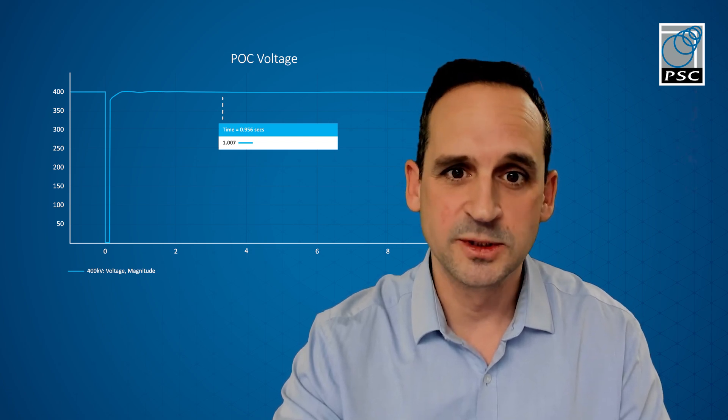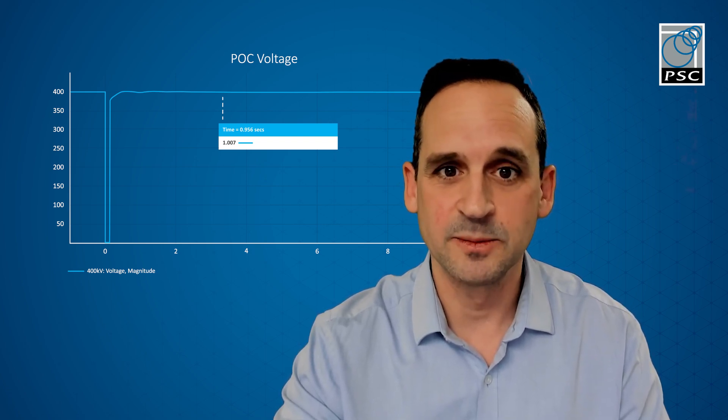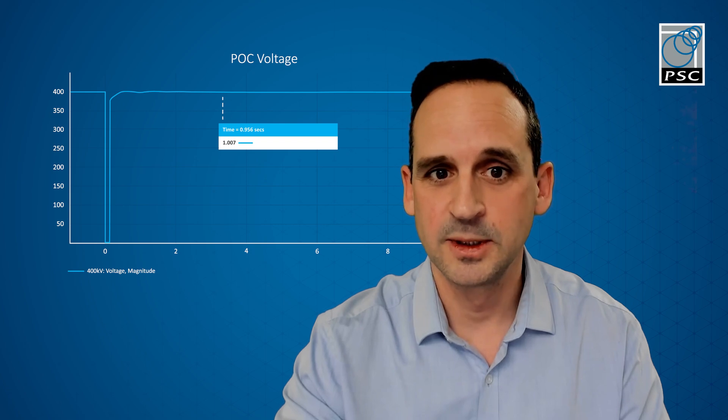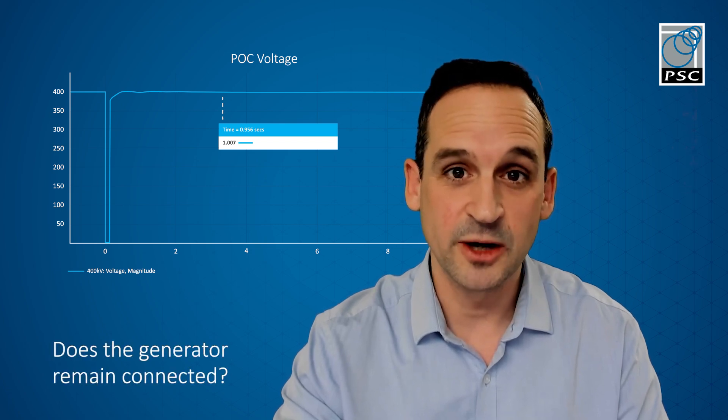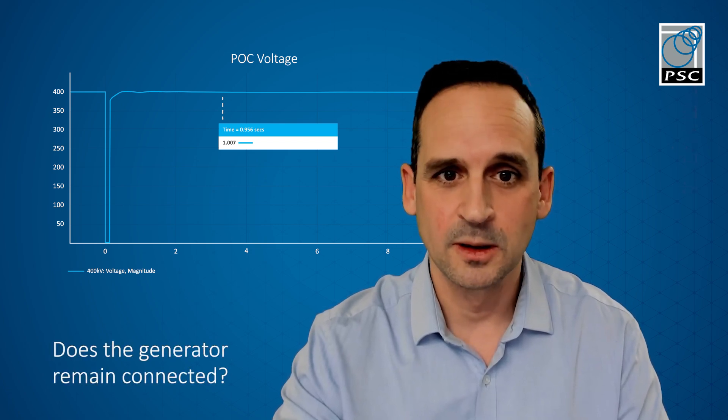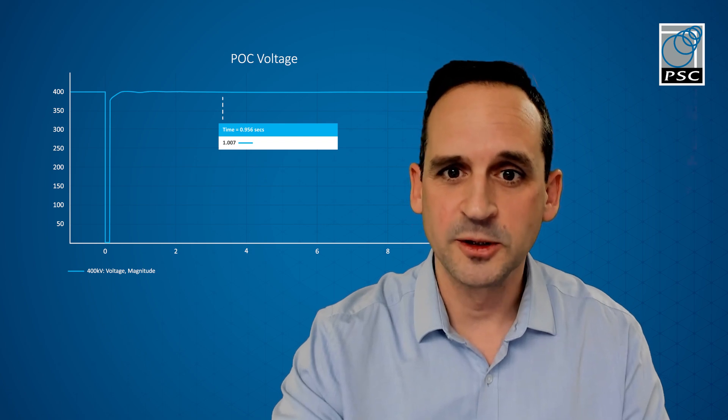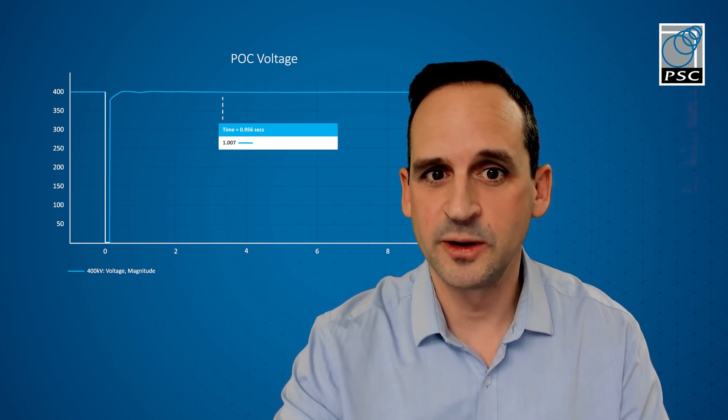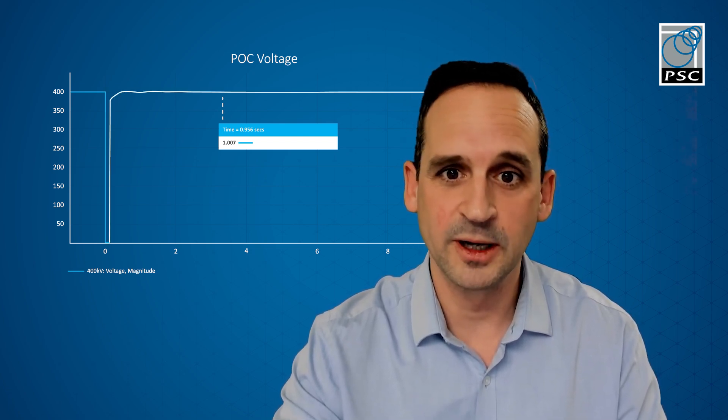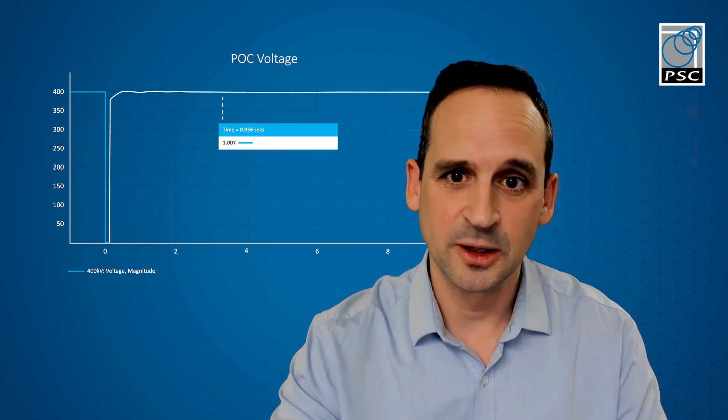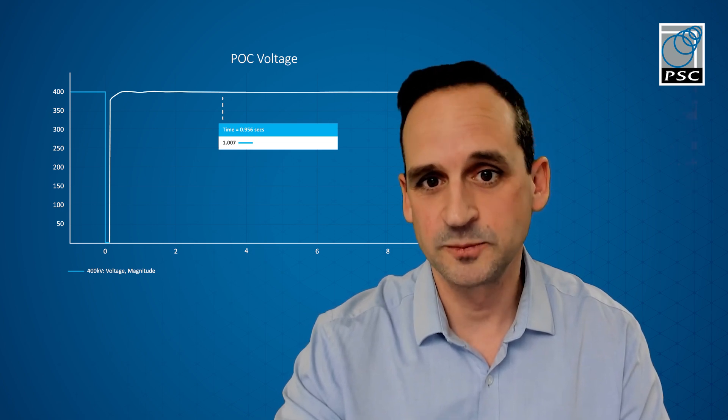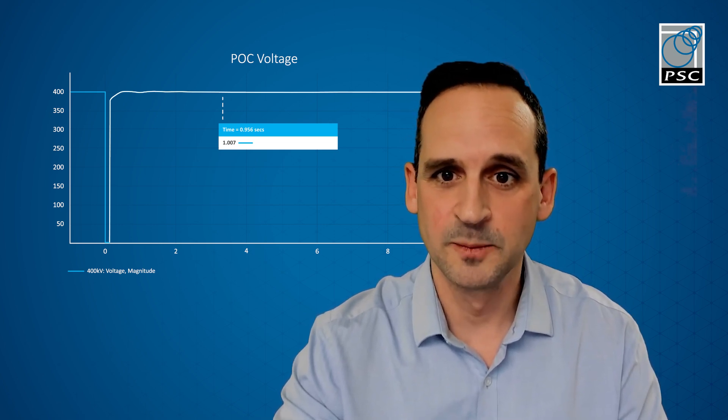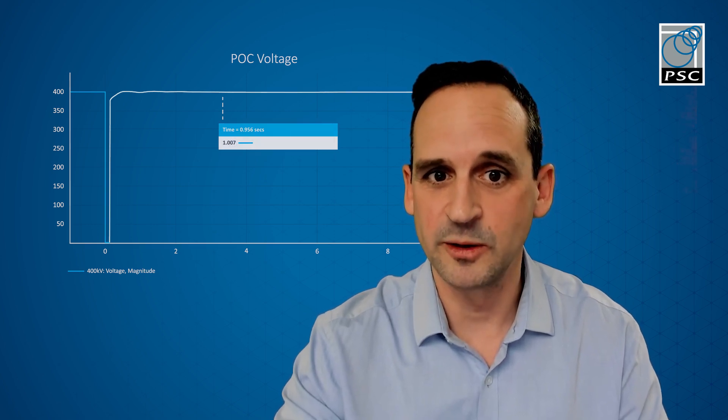If we look at these outputs from DigSILENT, we can check if it meets these three requirements. Firstly, does the generator remain connected? If we look at the generator voltage here, we can see that it drops during the fault and recovers following the fault clearance. You can see some initial overshoot due to the generator speeding up slightly, but the voltage settles down because the generator remains in synchronicity with the grid.